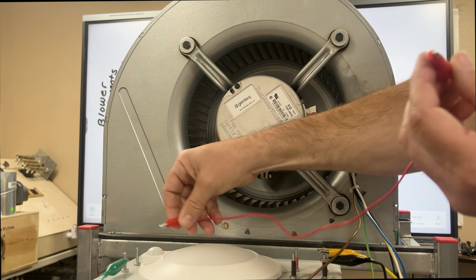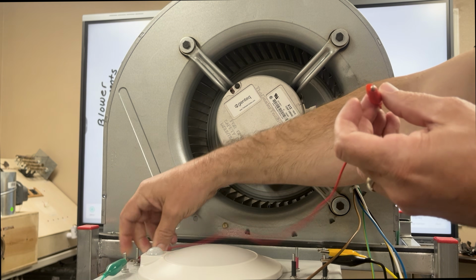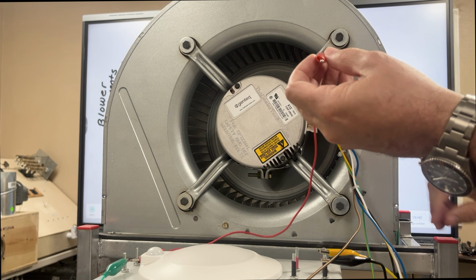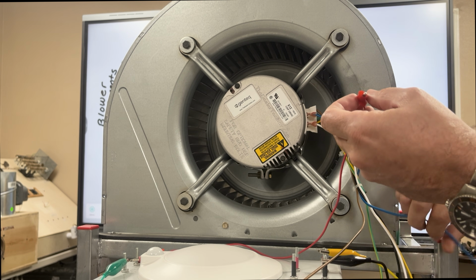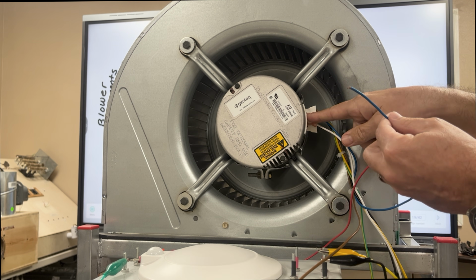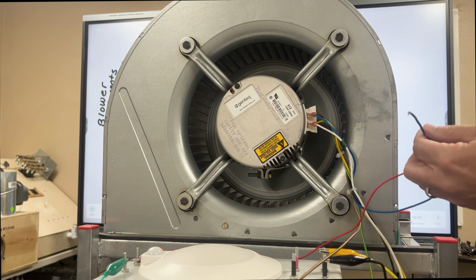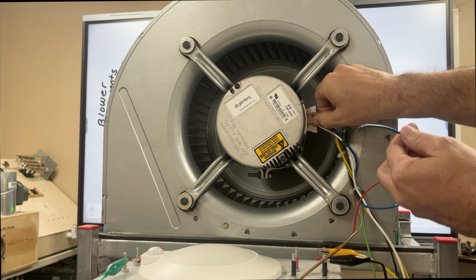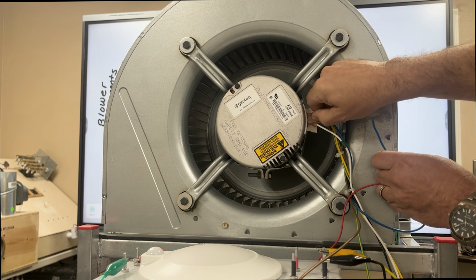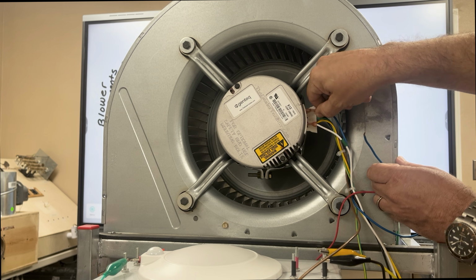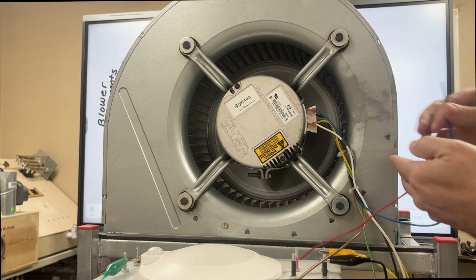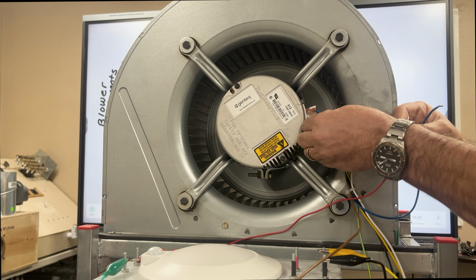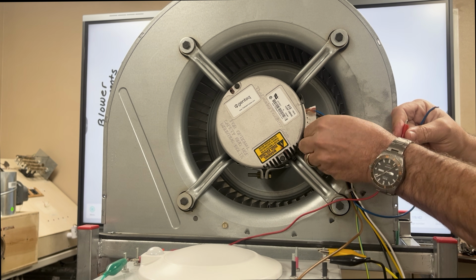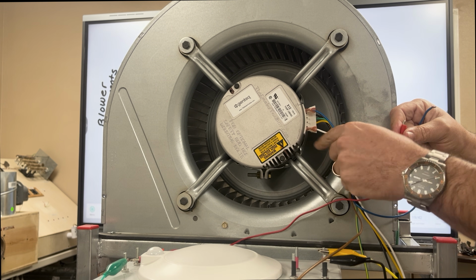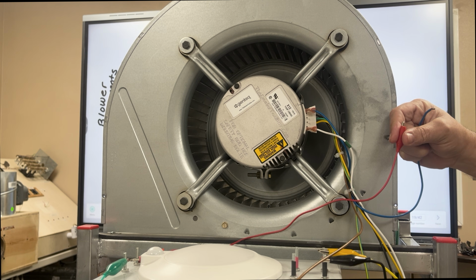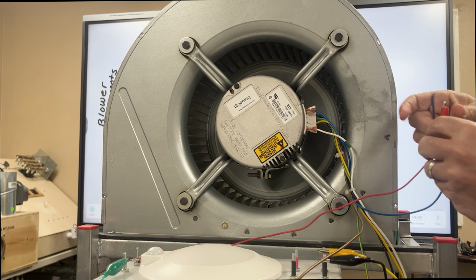And then we're going to take 24 volts, and I can hook this up to blue, which is on terminal 2. And just to help demonstrate with the acoustics, I'm going to take my blue wire, which is on 2, and hook it up to 1. And I'm going to take my white wire, which is on terminal 4, and put it down on 5, because there's a big difference between terminal 1 and terminal 5 as far as speed taps go. And I want you to be able to hear those acoustics.